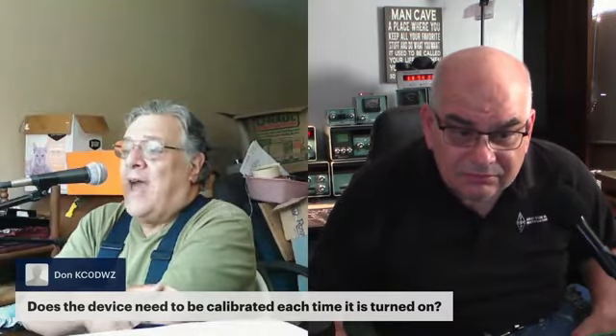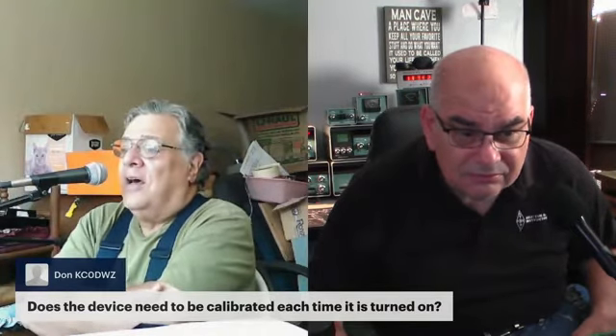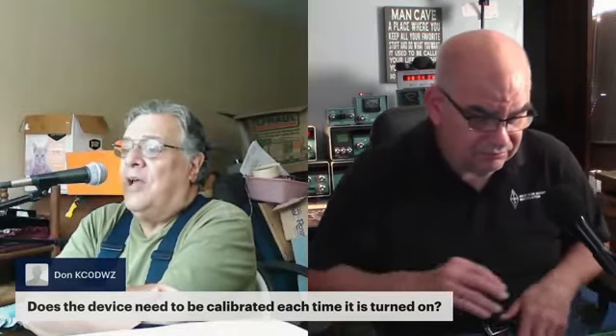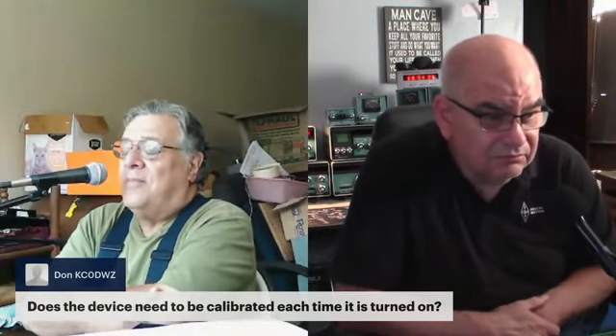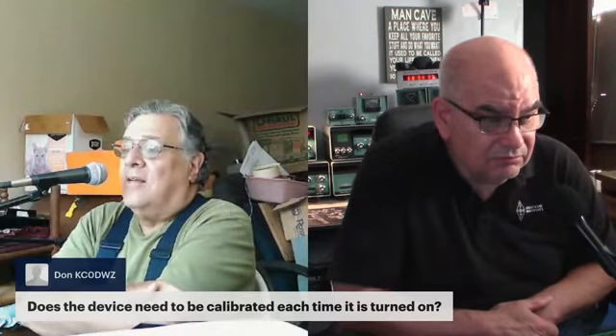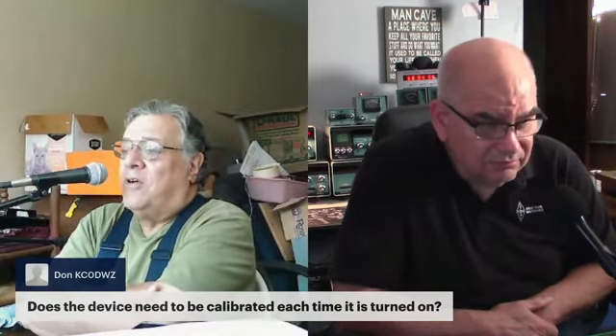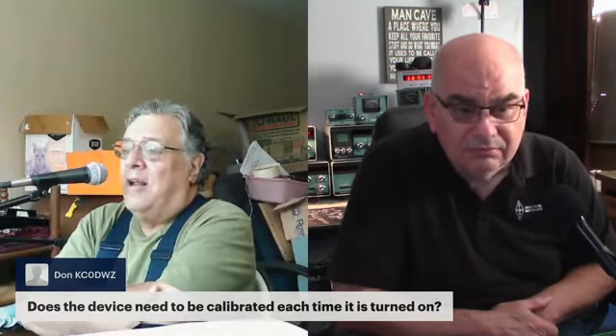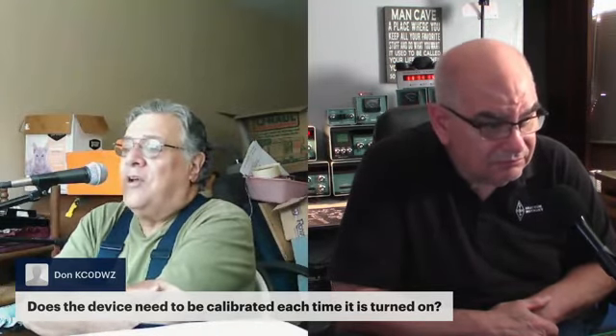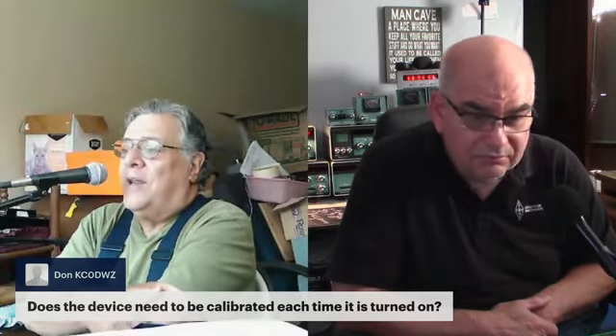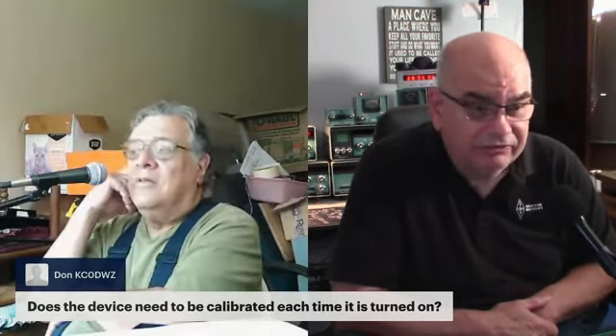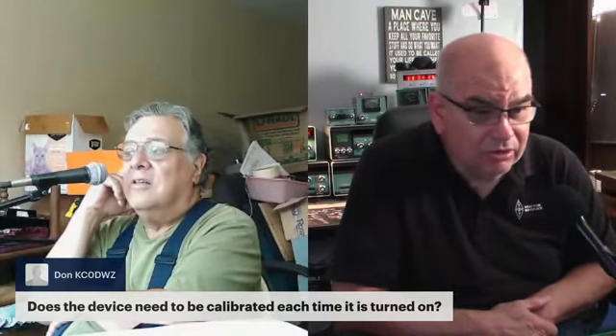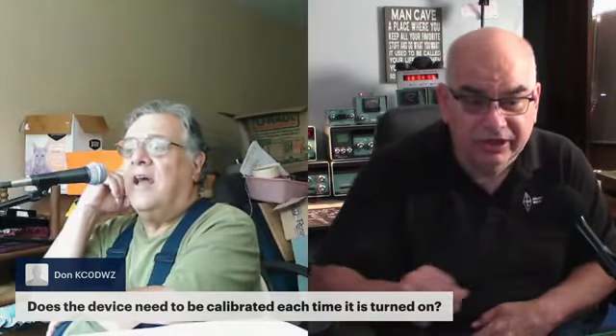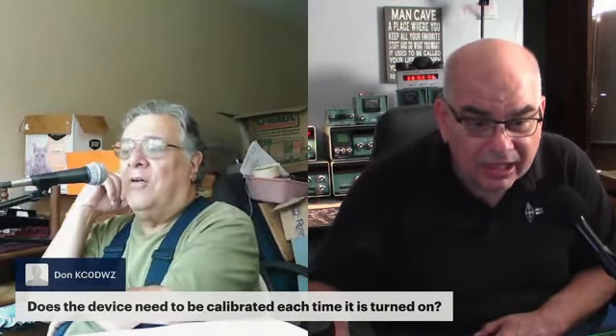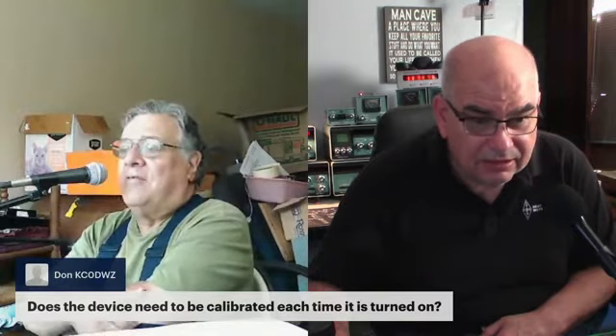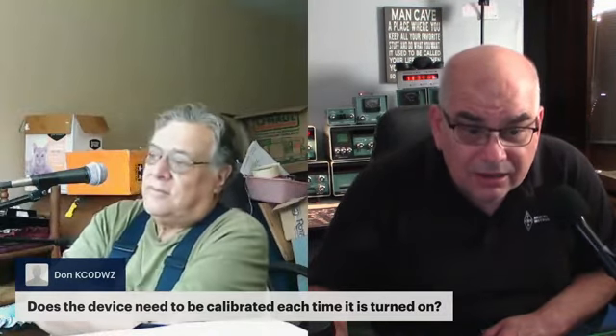Like I said, when you do the calibration, you can save that calibration in one of the memories, and then you can recall it as part of the setup. But like all RF instruments, they do drift over time. So if you calibrated a week ago, the calibration doesn't take that long to do, I would recommend doing it again. Not to mention, if you change anything like your frequency or any of the adapters, you should redo that calibration. Yeah, if you change anything in the cabling or the adapters or anything, then you have to do a recal.